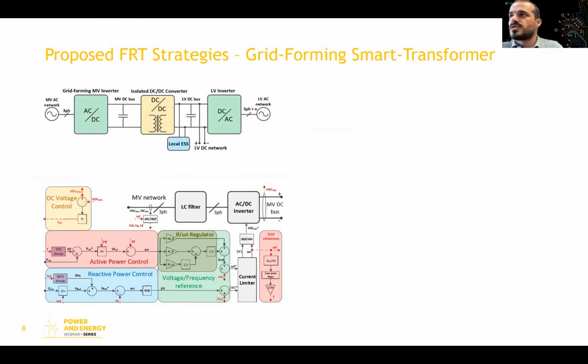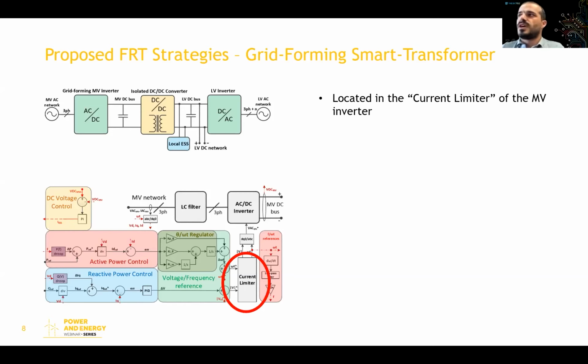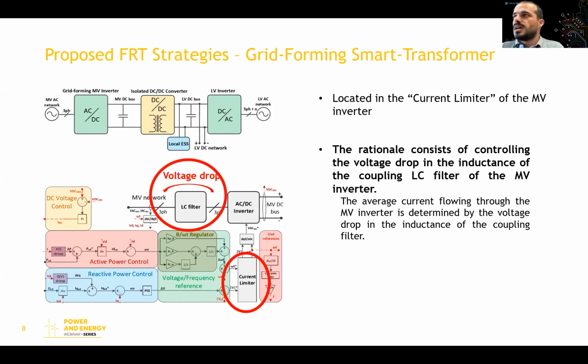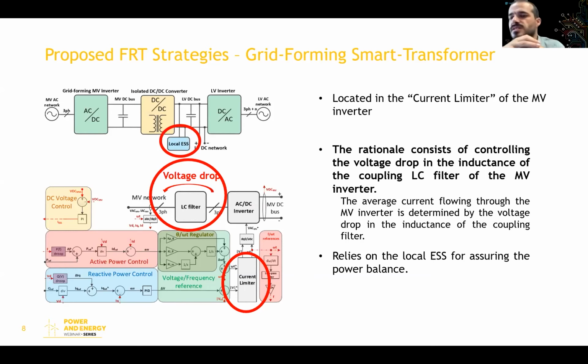Now about the grid-forming smart transformer. The proposed strategy is located in the current limiter, which is embedded in the medium voltage inverter. It exploits the fact that the average current flowing through the medium voltage inverter is determined by the voltage drop in the inductance of the coupling filter. So the rationale is to exploit this to ensure that the current limits of the medium voltage inverter are respected. And of course, in this case, it relies on the local energy storage system to ensure that the power balance is preserved.